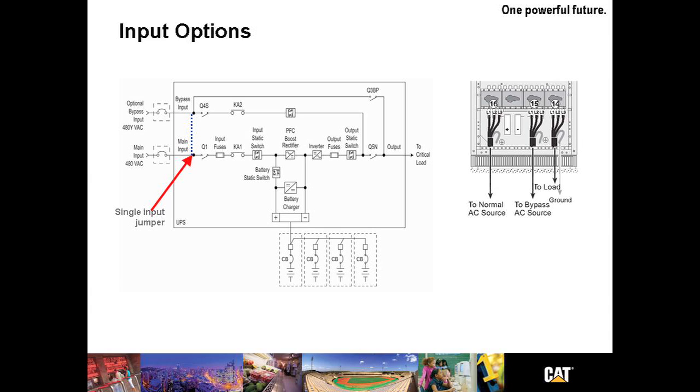One significant difference is that KA1 and KA2 are optional in the CAT UPS B125. You find this listed as backfeed protection. This pair of contactors provides isolation of the UPS from its utility source during discharge, and often required by local code.